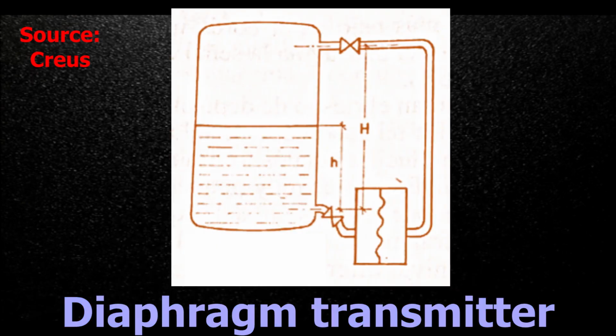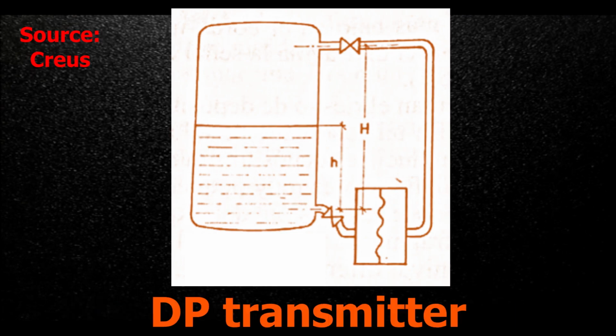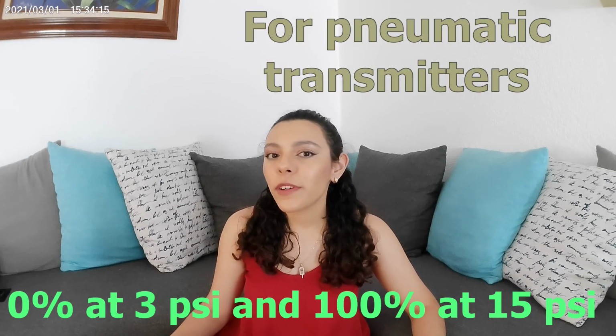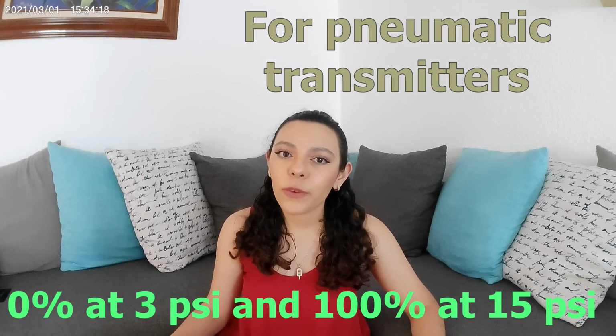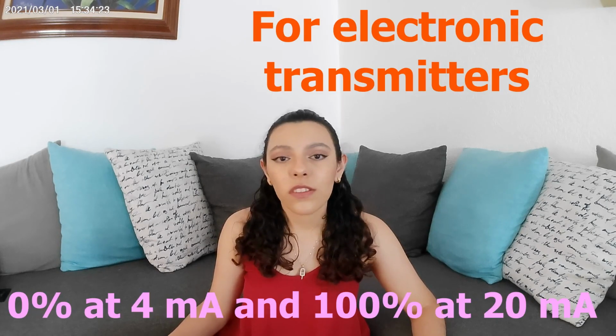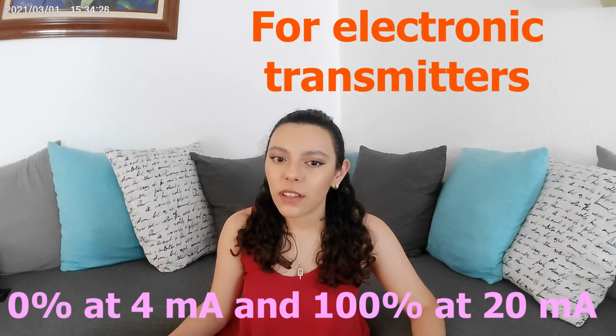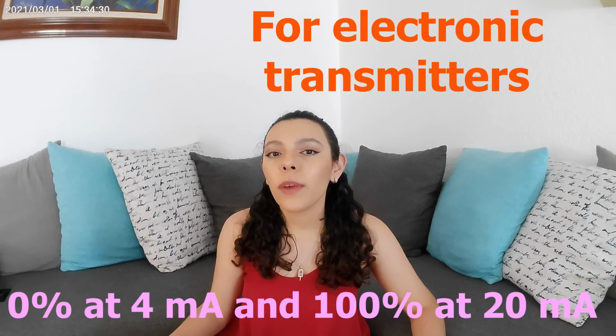When gases or vapors above the liquid are condensable, the line from the upper intake is gradually filled with a condensate until the entire tube is filled. Therefore, the pipe to the right of the transmitter will have more pressure than the one to the left and will mark low when it is high or vice versa. To solve this, we must set the instrument in reverse. That is, for pneumatic transmitters, it must indicate 0% at 3 psi and 100% at 15 psi, or 0% at 4 milliamperes and 100% at 20 milliamperes DC.